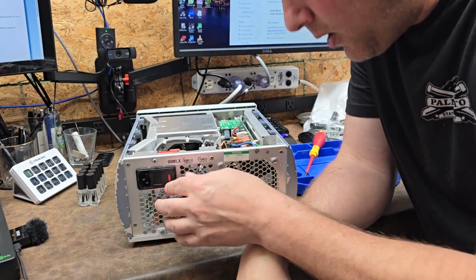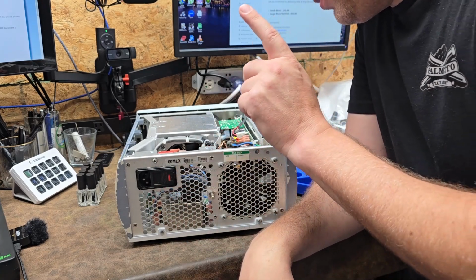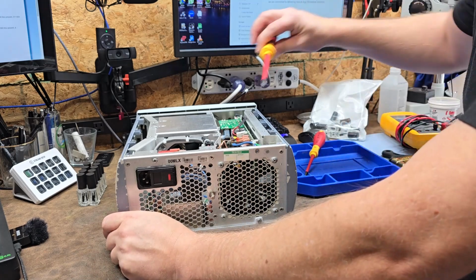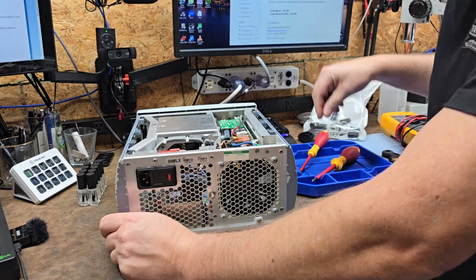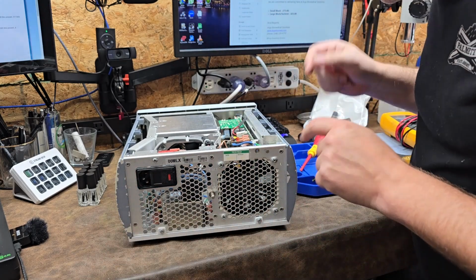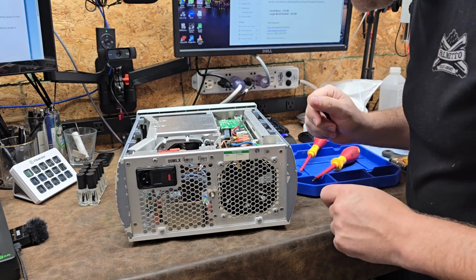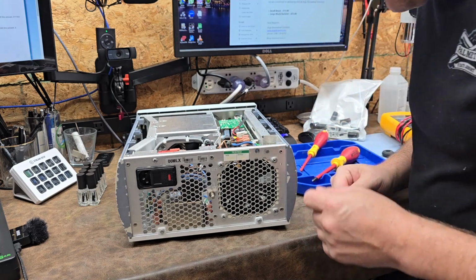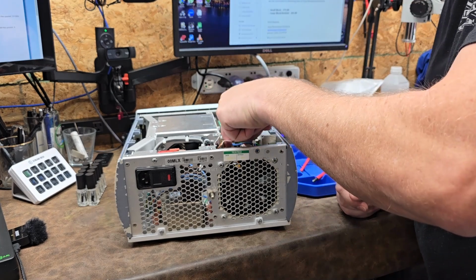Just because you hear the click doesn't necessarily mean AC mains is getting through, so to be sure, we will get a probe and check for AC power all the way to right here. Now I can see that my neutral is kind of sliding off right there, it's kind of off, so I'm going to be careful.